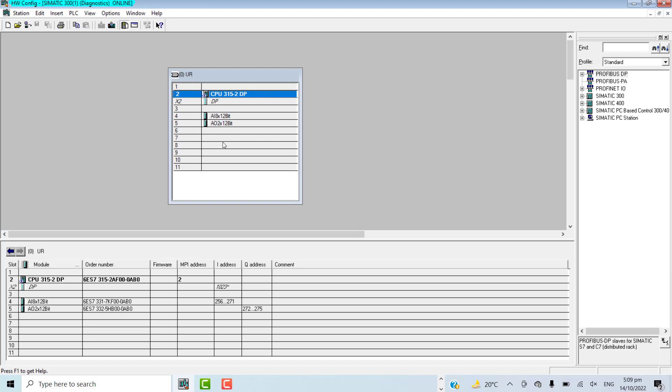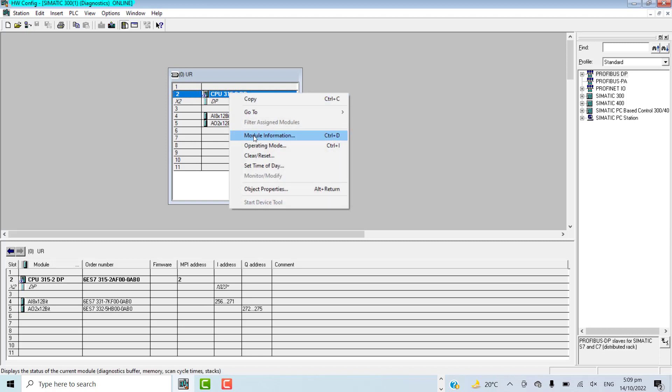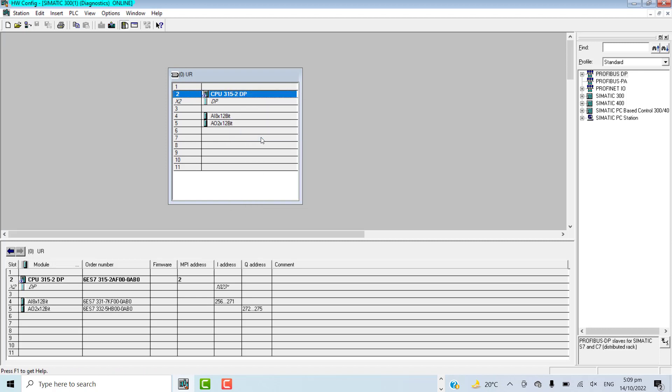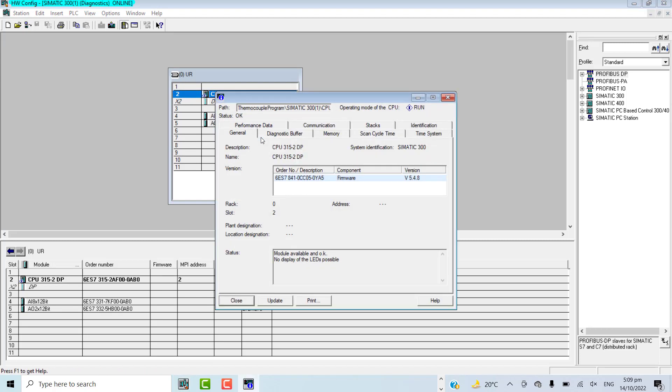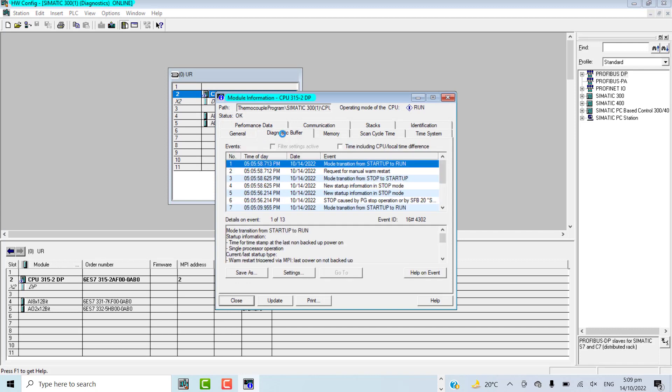The first step is to save the diagnostic buffer so we can have a look at the events that have caused the PLC stoppage or any other PLC problem. To go to the diagnostic buffer, you switch to online mode and click on the CPU. Right-click and go to module information. Here you can click diagnostic buffer.